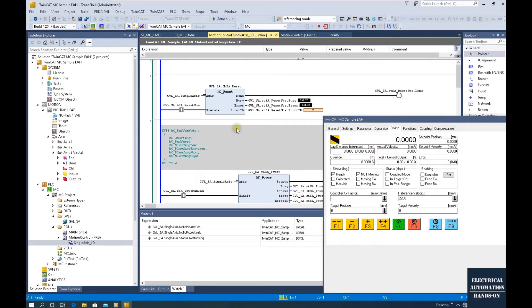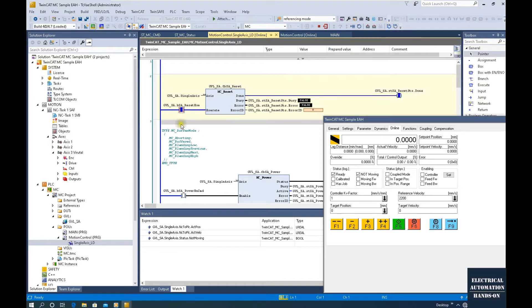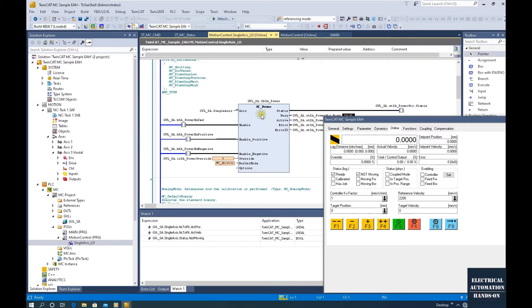Now let's go to test. Firstly, we can reset our axis. The system is running, we can see it has started already. In actual cases, we will connect this variable with the MCP push button, so once we click the push button, it will reset any errors from this axis. And then the MC_Power up could come from an enable button from the HMI. Here — power on. Also, this power on could be controlled by safety.